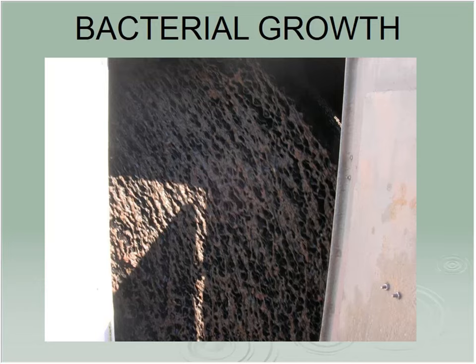This one is actually operating. It's hard to tell. If you were to see it in better lighting, you'd see there's some reddish areas inside this slime that's hanging on the disc. That indicates that they were nitrifying at the time.